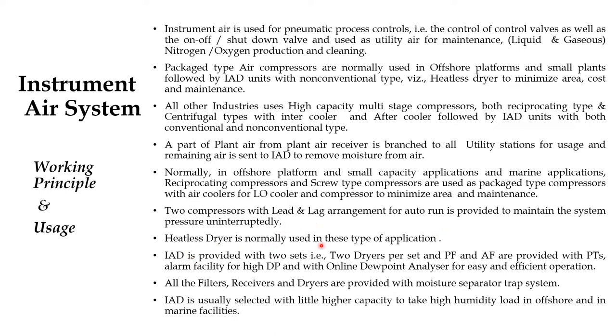Heatless dryers are normally used in these types of applications in offshore, marine and small industries. The instrument air dryer is provided with two sets of dryers, and per set two dryers are there. Two pre-filters and after-filters are provided with an alarm for high differential pressure and with an online dew point analyzer for easy and efficient operation in offshore and marine facilities.